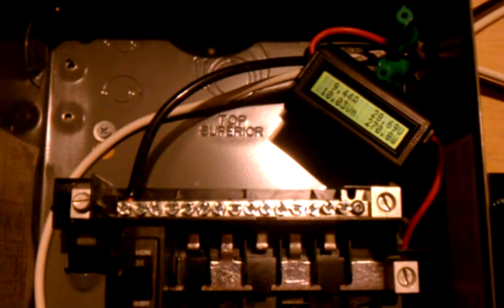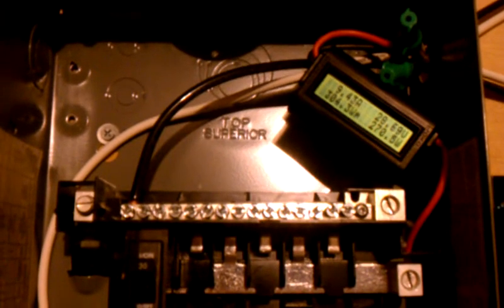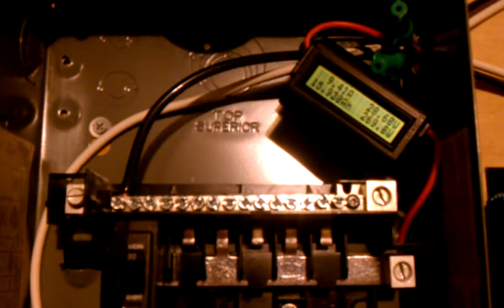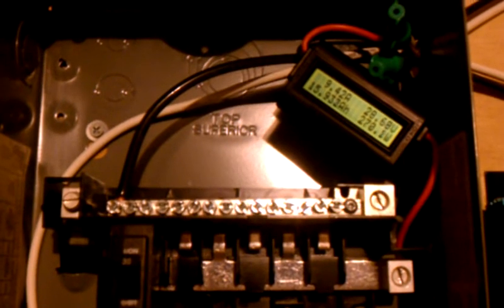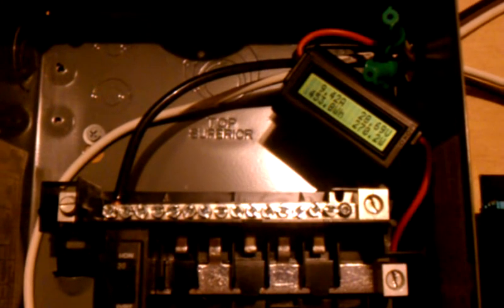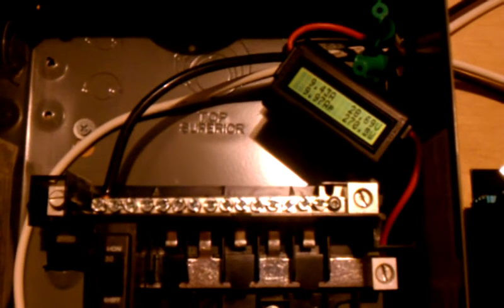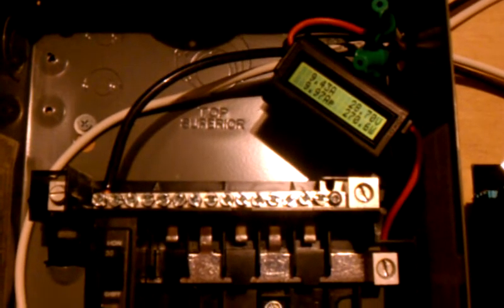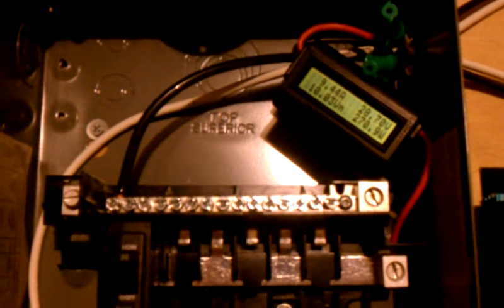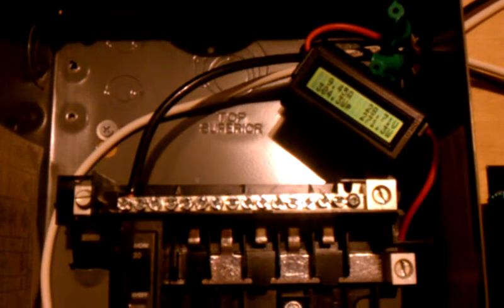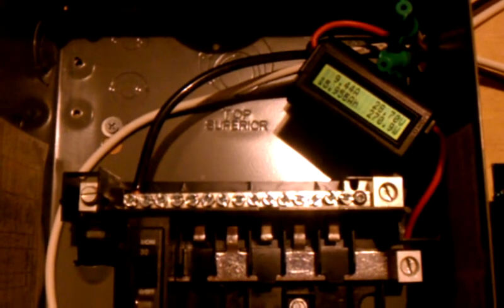So I'm thinking now I'm going to get a 15 amp breaker because I think a 10 might trip. It's been really cloudy today, so on a really sunny day, I might actually end up pulling more than 10 amps. I'm going to try a 15 amp breaker and go from there.